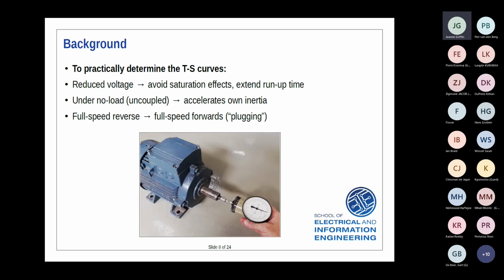It becomes a bit of a trade-off because you need the voltage low enough so the machine doesn't saturate, but high enough that it can produce enough torque to overcome stiction, otherwise it doesn't accelerate at all. Sometimes it also gets stuck at a harmonic torque, where it doesn't quite accelerate to full speed, it just gets stuck at a certain speed. So the voltage has to be low enough, but also high enough to get it to accelerate to full speed. And it's done under no load, normally completely uncoupled mechanically from the load, so it's effectively just accelerating its own inertia.